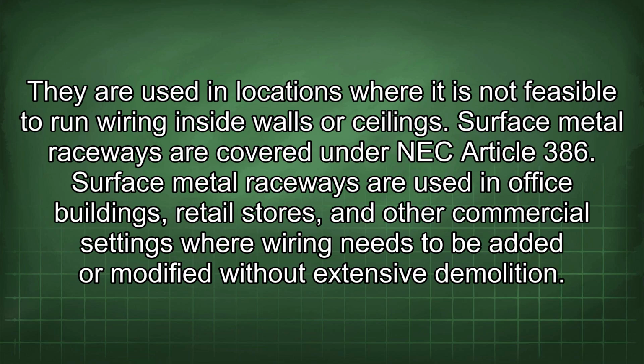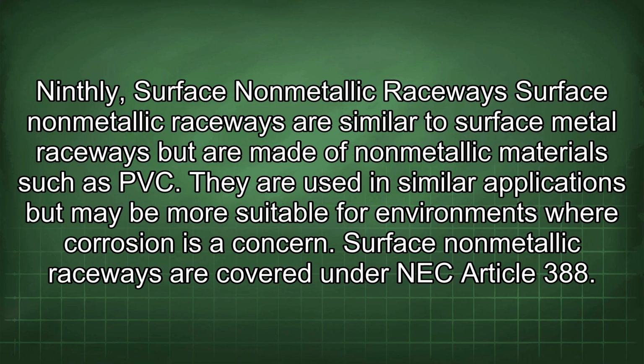Surface metal raceways are covered under NEC Article 386. Surface metal raceways are used in office buildings, retail stores, and other commercial settings where wiring needs to be added or modified without extensive demolition. Ninthly, surface non-metallic raceways. Surface non-metallic raceways are similar to surface metal raceways but are made of non-metallic materials such as PVC. They are used in similar applications but may be more suitable for environments where corrosion is a concern.